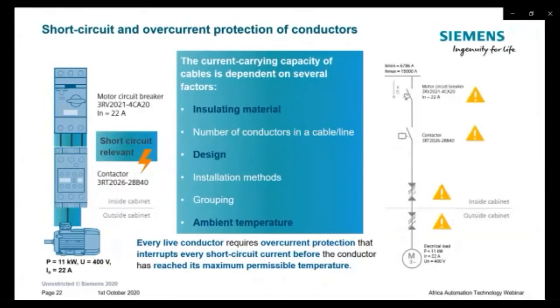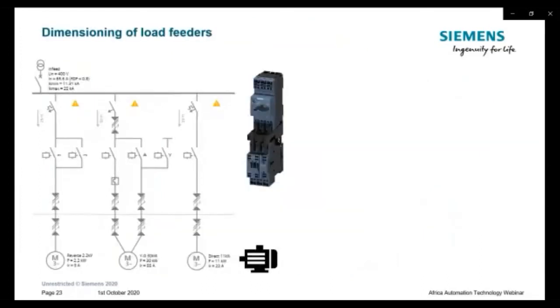So for this example, we identified the right motor circuit breaker as the protection device and the conductor, and the task is to identify the minimum required cross-section of the conductor material in line with those factors shown here in the middle of the slide. Dimensioning of load feeders goes very easy if you have the right knowledge or if you have the right tools. Load feeder dimensioning requires precise information and knowledge.